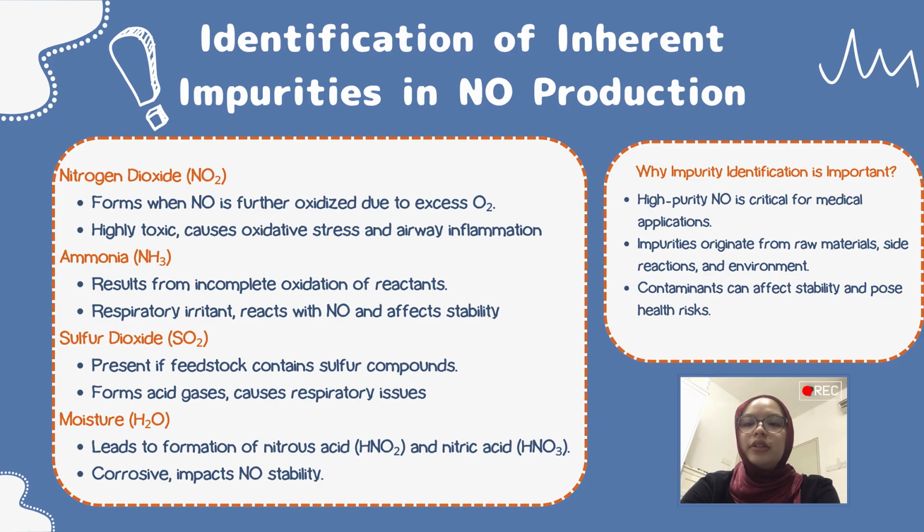Moisture and trace metals further contribute to unwanted reactions, leading to corrosion and chemical instability. Without effective purification, these impurities undermine therapeutic efficiency of NO. A robust purification system is necessary to meet strict medical safety and quality standards.